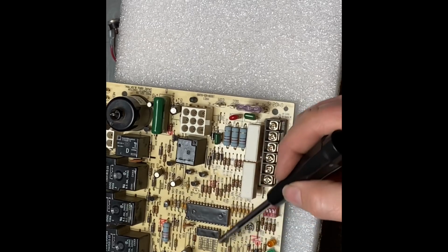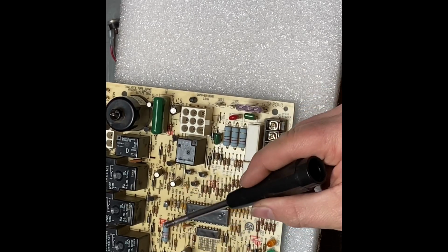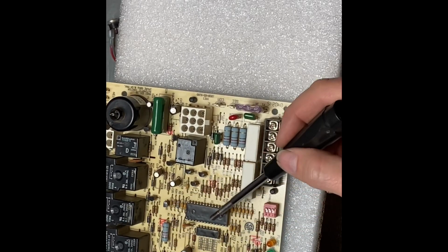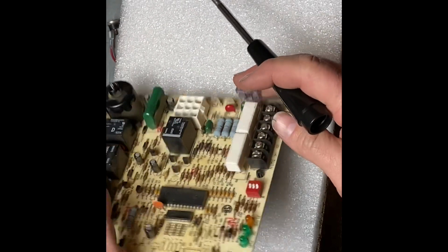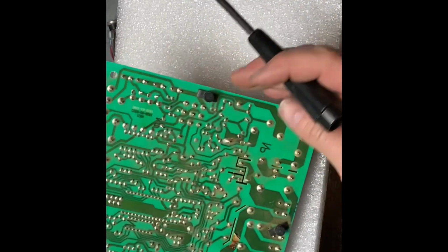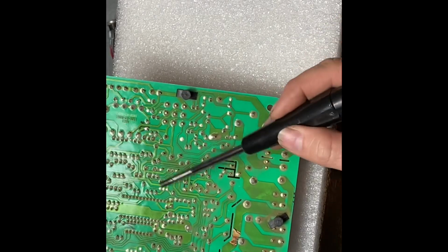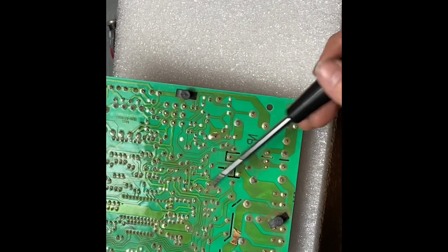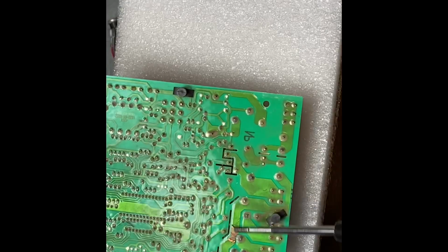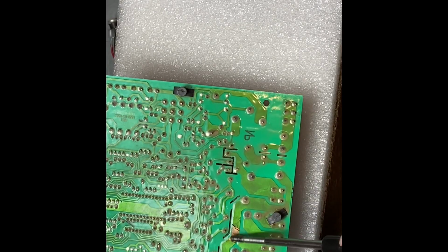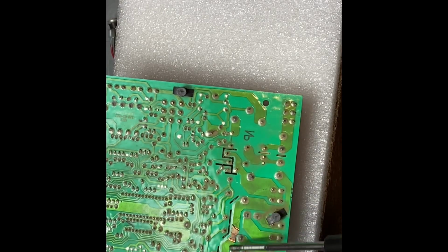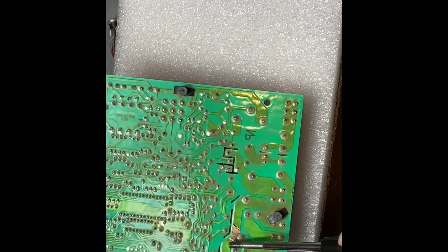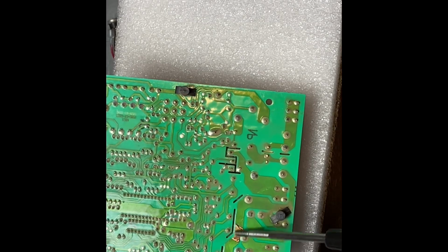The rest of the components on here are all just little capacitors, resistors, and the controls that make it think. If we're inspecting these units, we want to look on the back side. And on this board, there's a significant amount of dust. What I usually do is take a paintbrush and clean these off. But if you look right here, we have a significant burnt spot on this control board. So something at some point in time has ruined this board, overheated it, shorted it out. It's literally burned these connections.